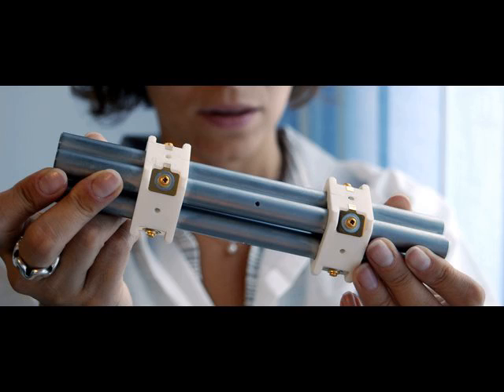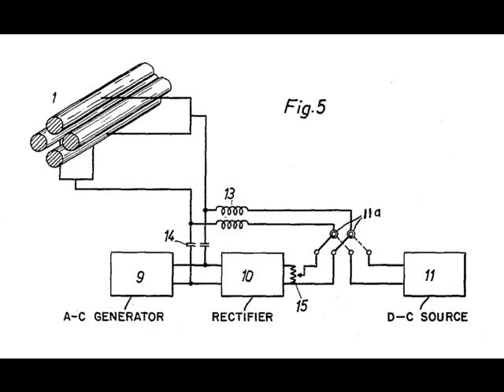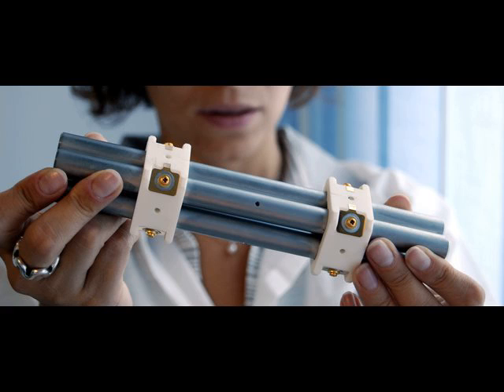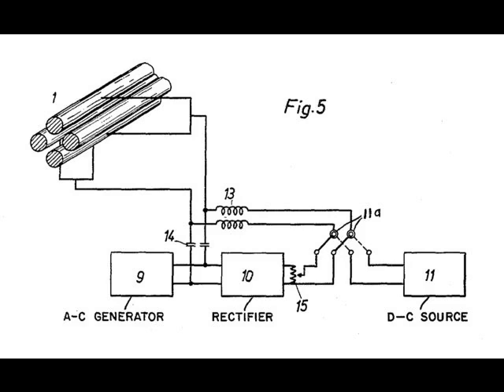The quadrupole mass analyzer is one type of mass analyzer used in mass spectrometry. As the name implies, it consists of four circular rods set parallel to each other. In a quadrupole mass spectrometer, the quadrupole is the component responsible for filtering sample ions based on their mass-to-charge ratio. Ions are separated based on the stability of their trajectories in the oscillating electric fields applied to the rods.